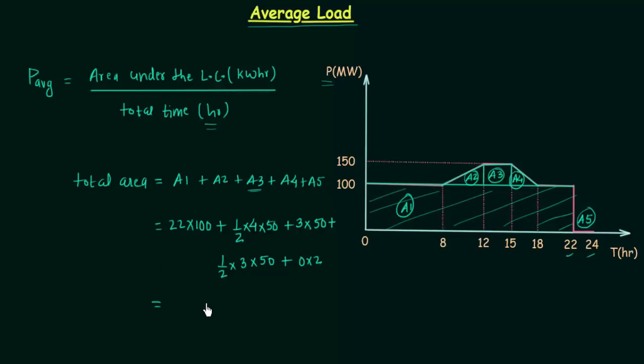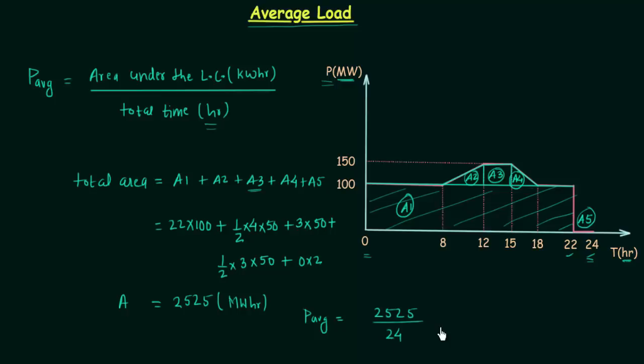Once you complete the calculation you get a total area of 2525 megawatt hours. Now to find average power, divide the total area by the total time of 24 hours. So average power equals 2525 divided by 24, which equals 105.2 megawatts. The unit is megawatts because the megawatt hours unit divided by hours leaves megawatts.